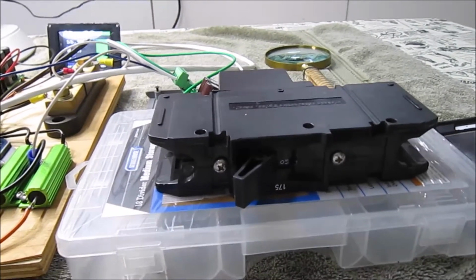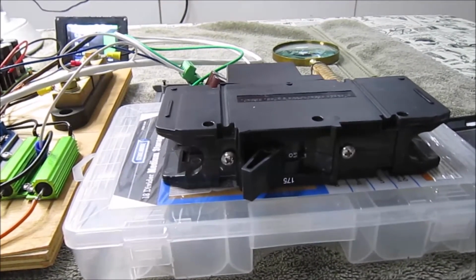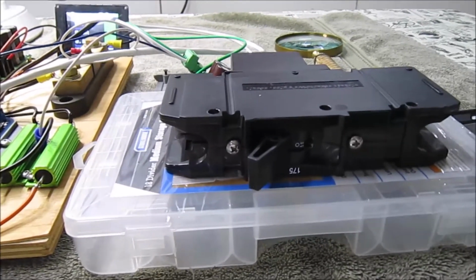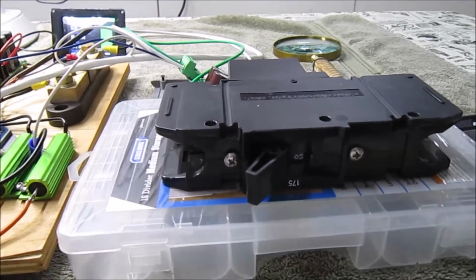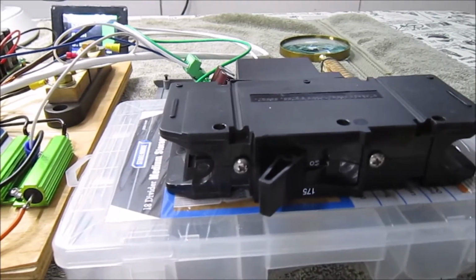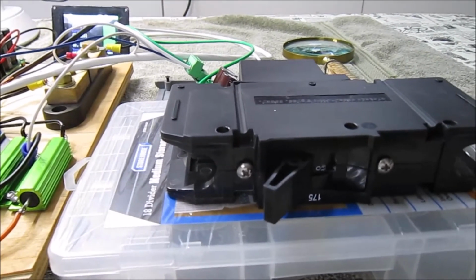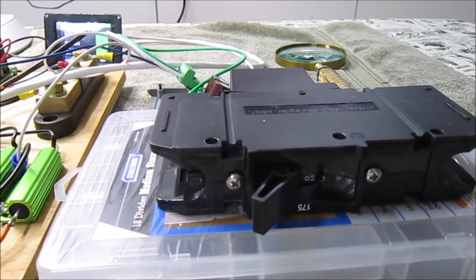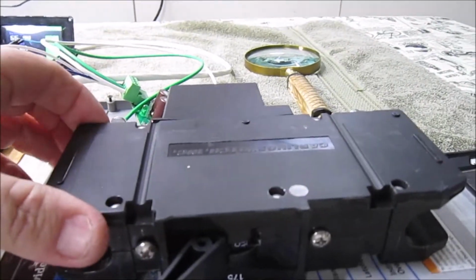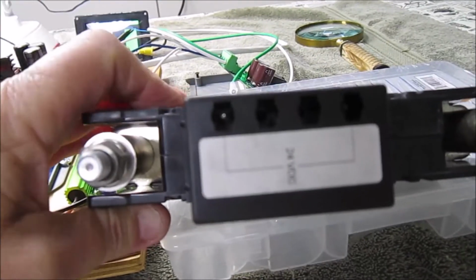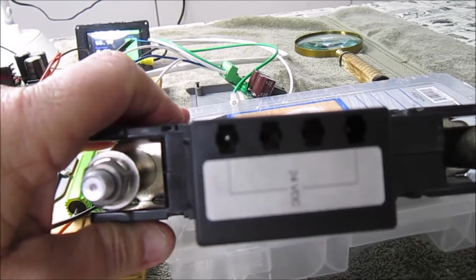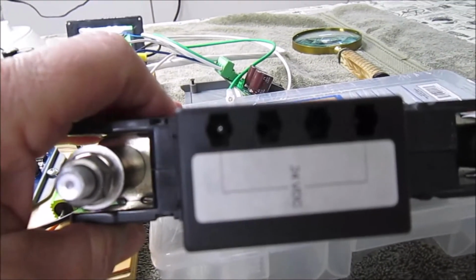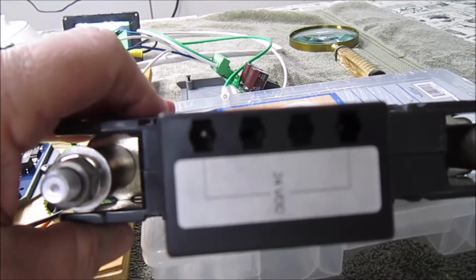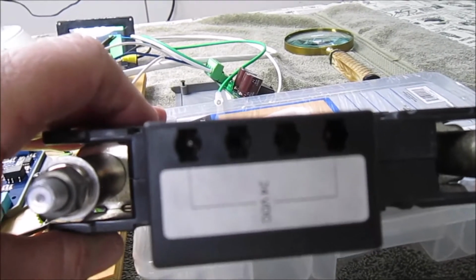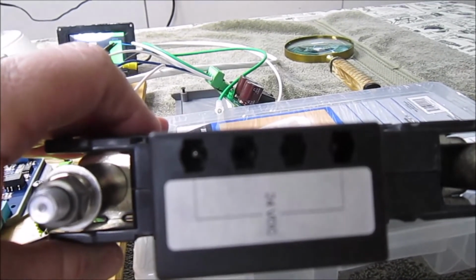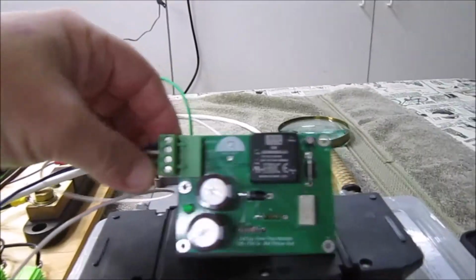Unlike some of the other brands, like for example Eaton or maybe a Square D or Schneider type breaker, they're configured so when they trip, the contact inside opens and it no longer feeds power to the coil. Unfortunately, this particular product has a limitation for the number of seconds or minutes you can hold power on the coil without burning it up. So it needs a pulse to activate it and then shut off.